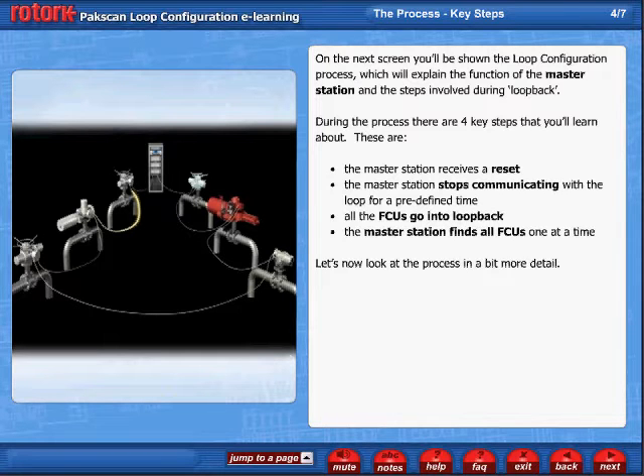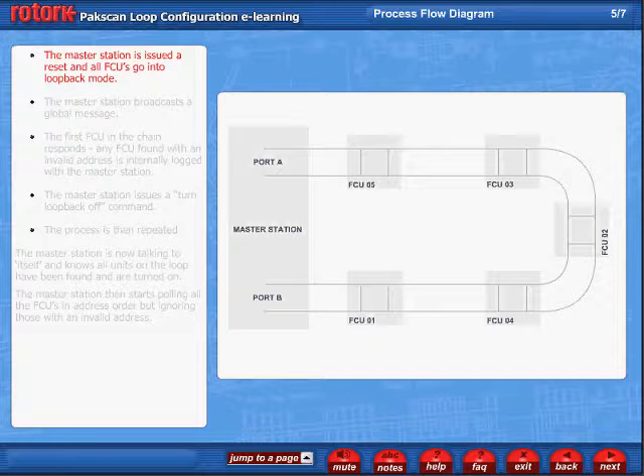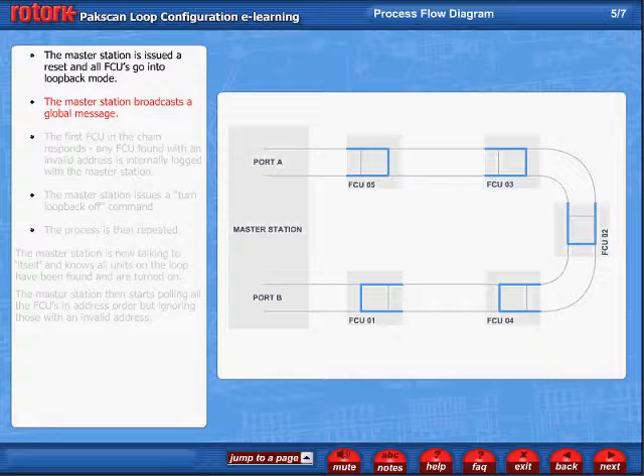Let's now look at the process in a bit more detail. The process starts when the master station is issued a reset and stops communicating with the FCUs. At this point, all the FCUs go into loopback mode. The master station now broadcasts a global message stating: respond if you are in loopback.